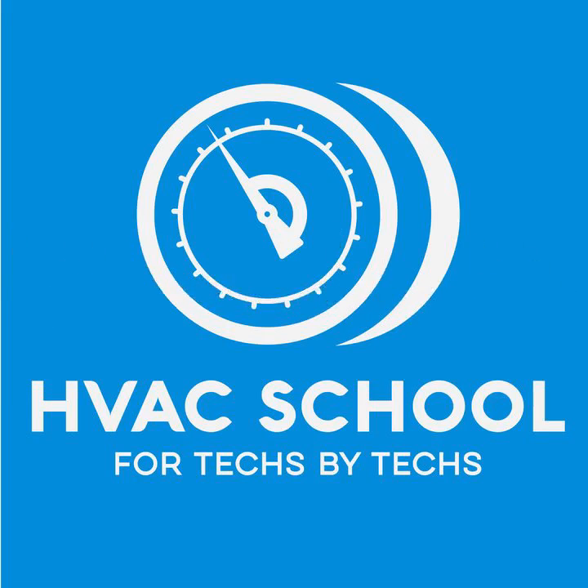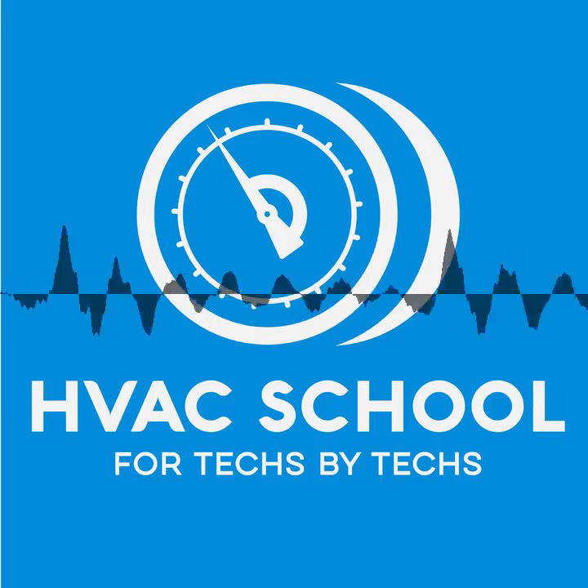And that's a great tech tip we can throw in here, right? That it's doing two things. One, you're checking your bulb charge to see if it's still good, right? But two, it's one of those last-ditch things you can do: instead of dialing your superheat all the way in, till the screw practically falls out, just hold that bulb in your hand. And if the valve's got some crud in the actual stem somewhere that's causing a lot of hysteresis, you can apply enough pressure differential across it by the heat of your hand to often overcome that gumminess and unstick the valve.